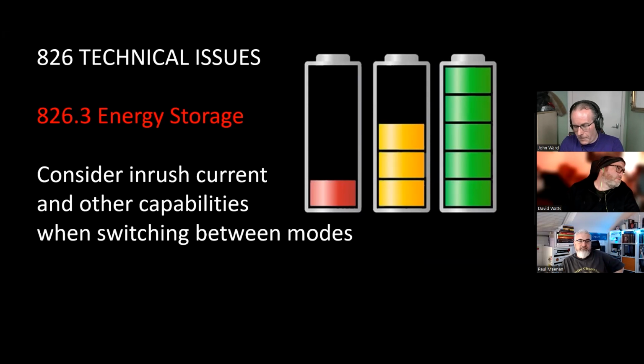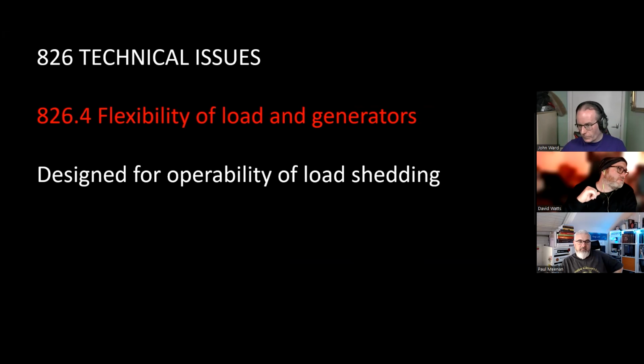Energy storage. You need to consider the inrush current and other capabilities when switching between modes, because if you're taking something off load and putting something on, again, it's not just turning on, say, 20 amps of load. You could have a very high inrush current there when you're changing between the different modes. And flexibility of loads and generators. Are they actually designed to operate with load shedding? So you can have things like, if your load is too high to work with your, say, battery storage, it needs to disconnect some of those items or reconnect them if possible.